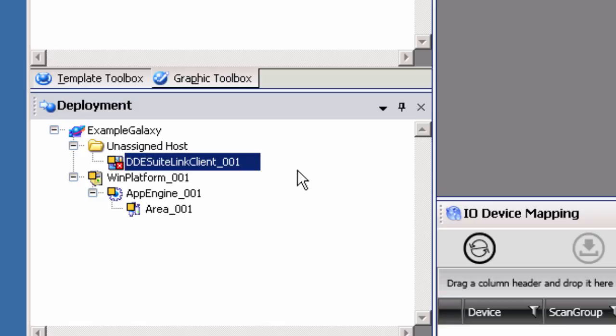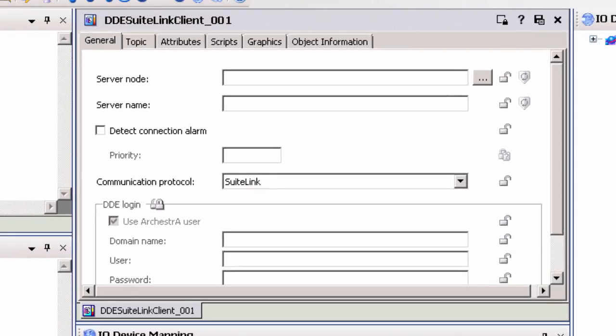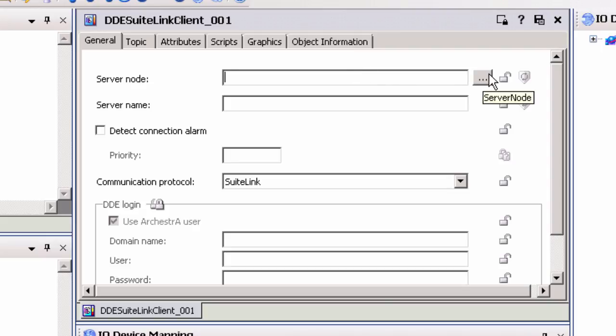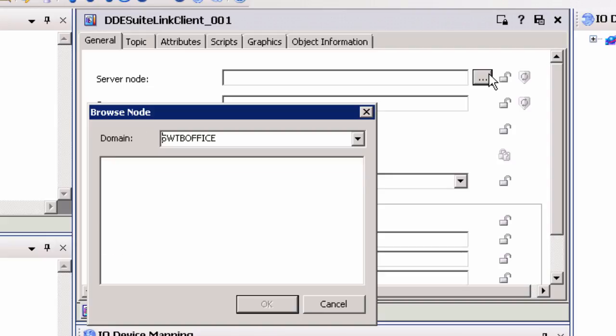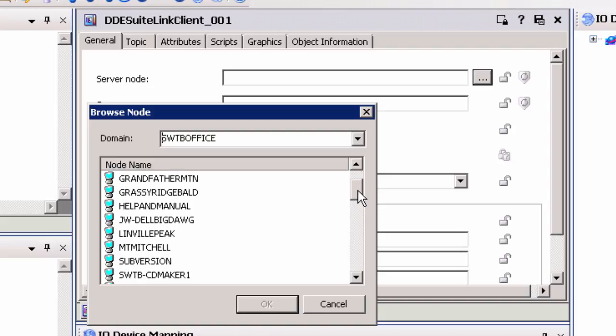Double-click the DDE SuiteLink Client Object under the Unassigned Host to open the Object Properties to the right of the Template Toolbox. If the TopServer and System Platform are located on the same PC, leave the Server Node blank. If not, click on the Ellipses button to the right of the Server Node text field to open the Browse Node dialog box.